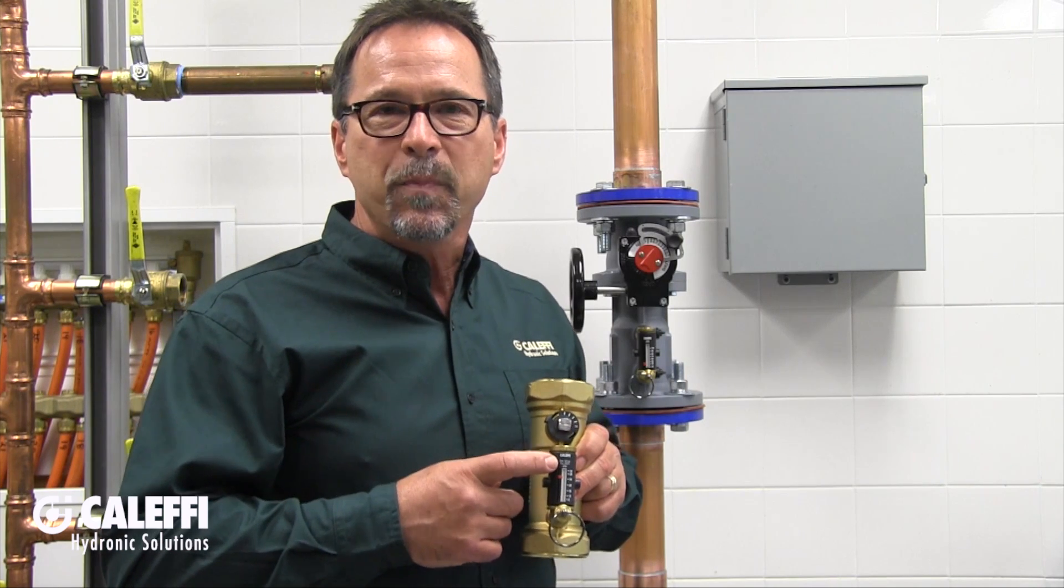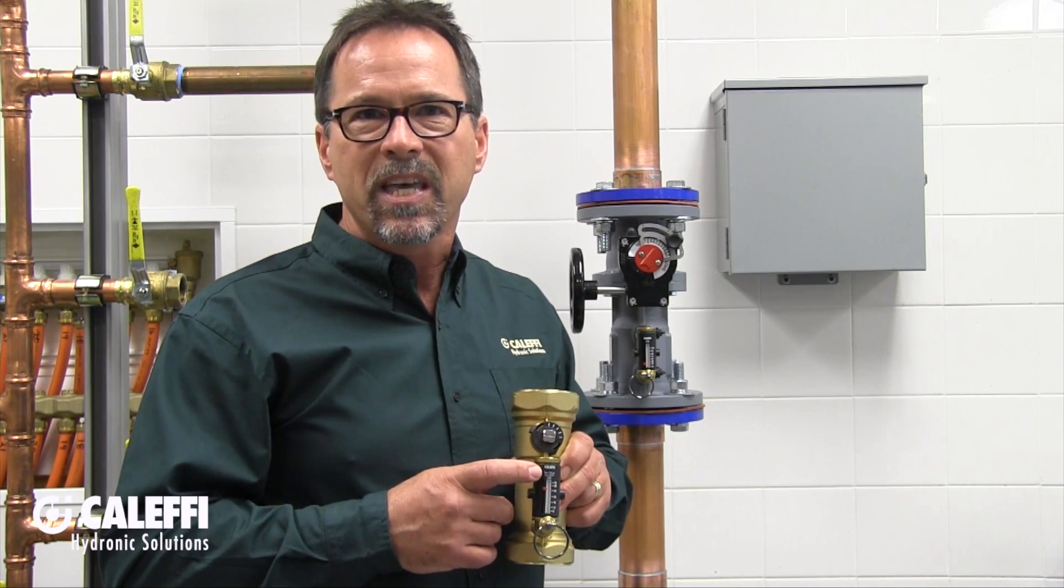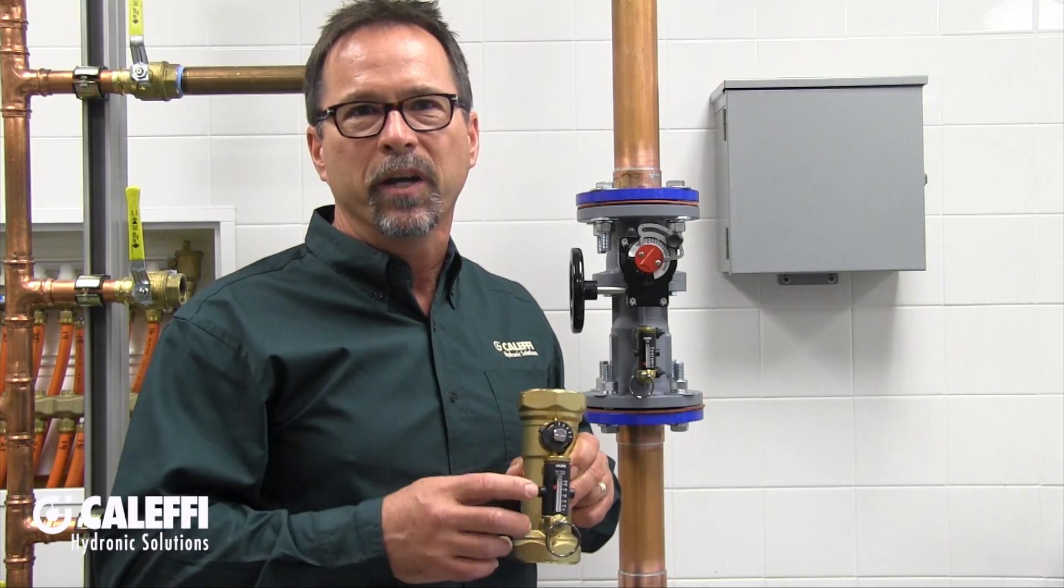like our brass threaded version, it has an integral flow meter. This means you do not have to have a differential pressure tool or any charts or graphs to balance your hydronic system. The integral flow meter is the key feature that differentiates this product from all others.